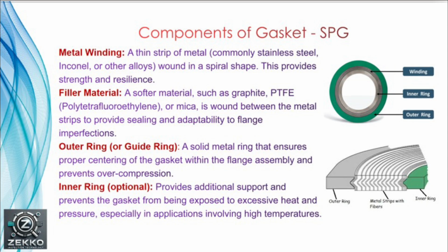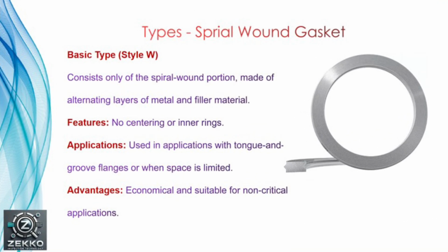So here we will see the new topic, types of spiral wound gasket. There are four types of spiral wound gasket. The first type is the basic type, which is also called style W. It consists only of the spiral wound portion made up of alternating layers of metal and filler material. There is no center or inner ring for this gasket. It is widely used in applications of tongue and groove flanges or where space is very limited. Basically, the advantage is that it is economical and suitable for non-critical applications.